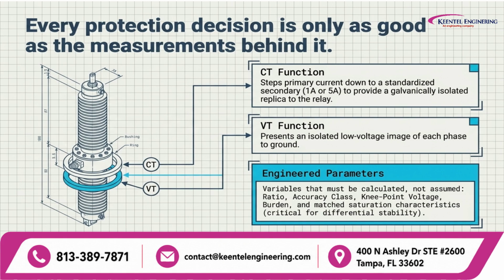Several parameters must be calculated and verified. These include the CT ratio, accuracy class, knee point voltage, burden, and the saturation characteristics of the CTs. This is especially important for transformer differential protection. If CTs saturate differently during a fault, the relay can see an artificial differential current. That can create either a security problem, where the relay trips unnecessarily, or a dependability problem, where the relay fails to respond correctly. Therefore, measurement engineering is not a supporting detail. It is the foundation on which the entire protection decision is built.